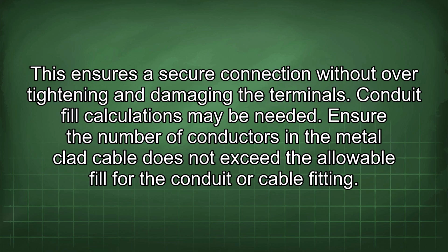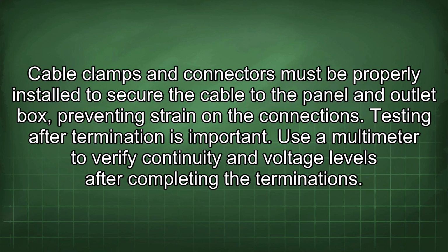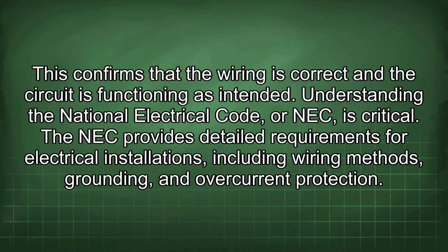Conduit fill calculations may be needed. Ensure the number of conductors in the metal-clad cable does not exceed the allowable fill for the conduit or cable fitting. Cable clamps and connectors must be properly installed to secure the cable to the panel and outlet box, preventing strain on the connections. Testing after termination is important. Use a multimeter to verify continuity and voltage levels after completing the terminations. This confirms that the wiring is correct and the circuit is functioning as intended.